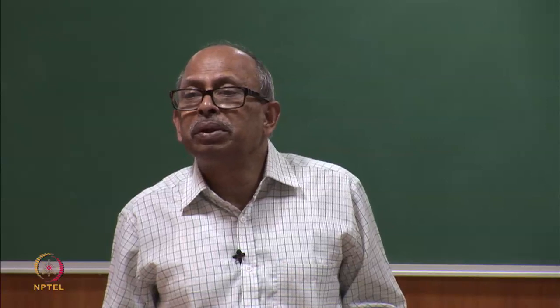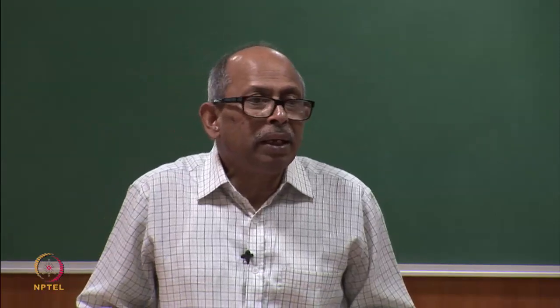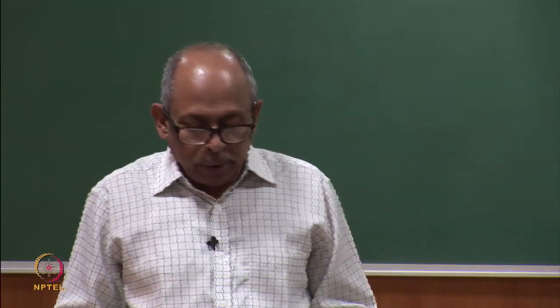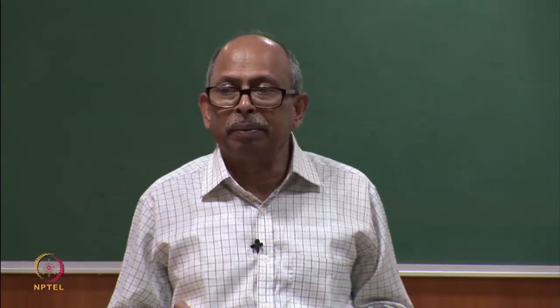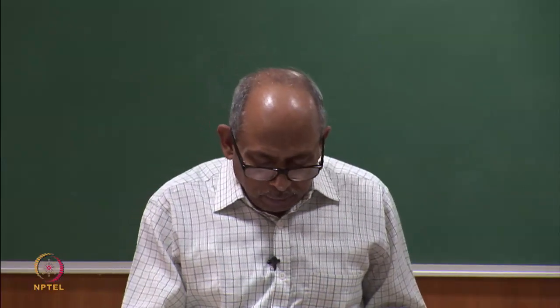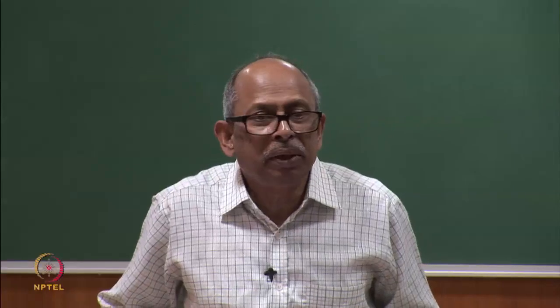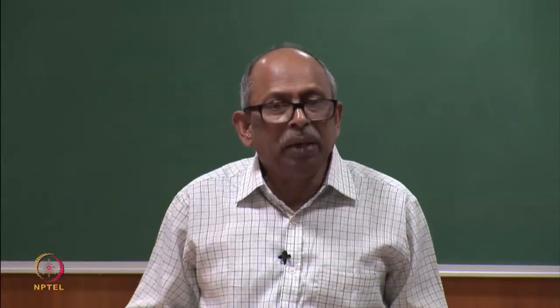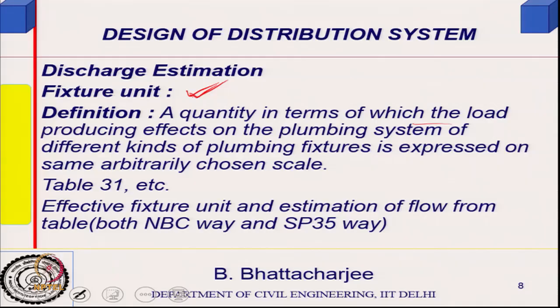The second issue is that frequency of use is also different — a kitchen tap might be used more often than a shower. Therefore, a new unit called the fixture unit is devised to make everything uniform in some manner. The fixture unit is a quantity in terms of which the load-producing effects of different kinds of plumbing fixtures are expressed on an arbitrary scale.